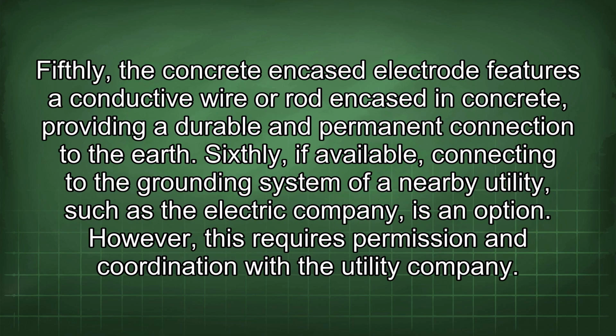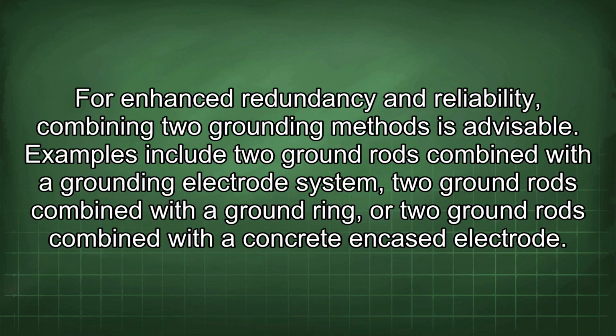Fifthly, the concrete encased electrode features a conductive wire or rod encased in concrete, providing a durable and permanent connection to the earth. Sixthly, if available, connecting to the grounding system of a nearby utility, such as the electric company, is an option. However, this requires permission and coordination with the utility company. For enhanced redundancy and reliability, combining two grounding methods is advisable. Examples include 2 ground rods combined with a grounding electrode system, 2 ground rods combined with a ground ring, or 2 ground rods combined with a concrete encased electrode.